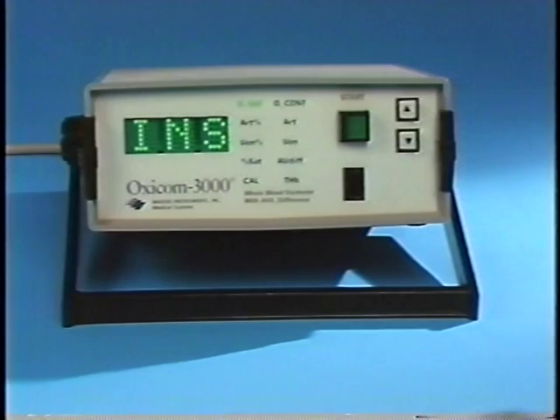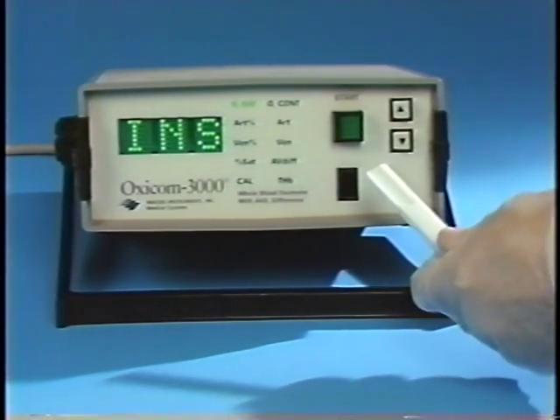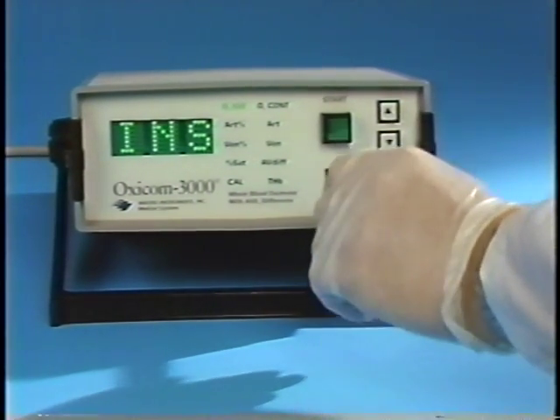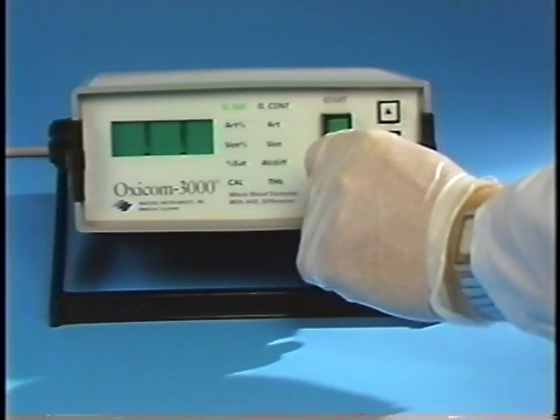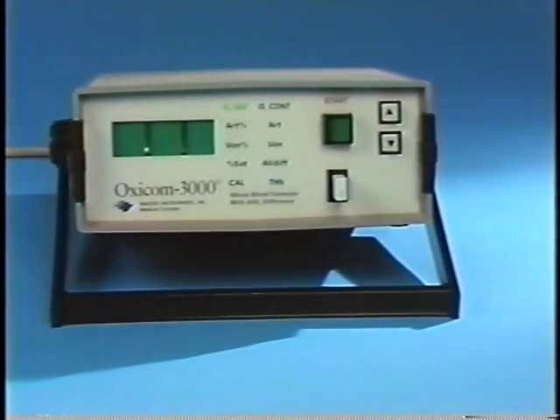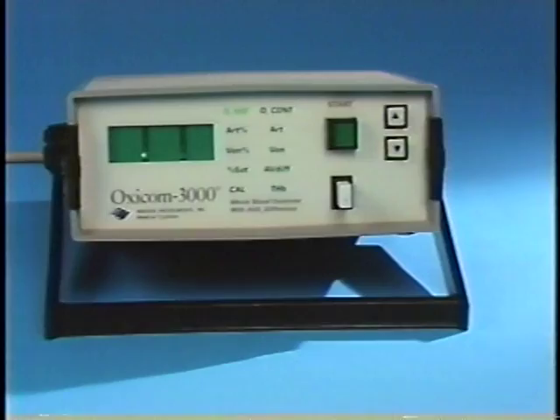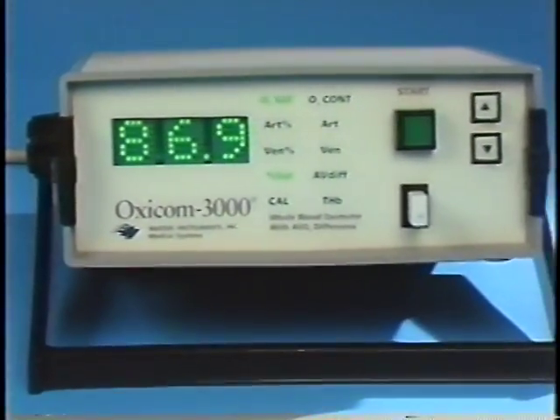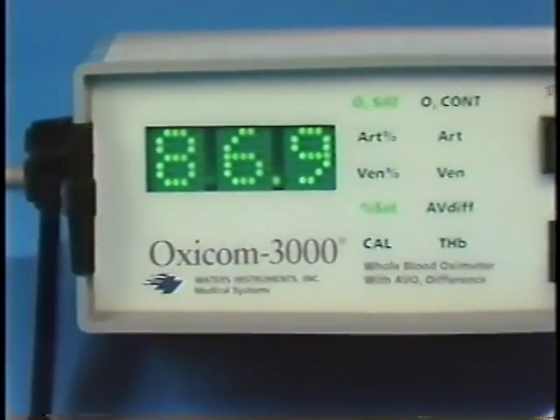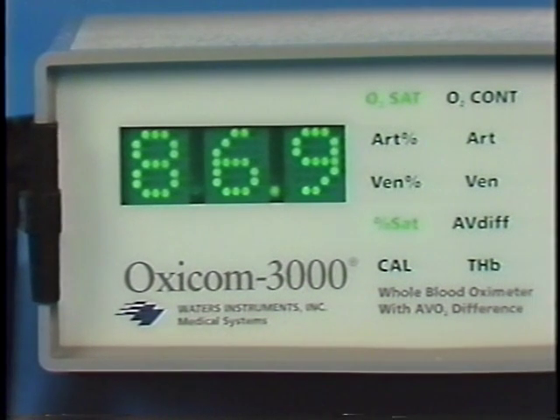The white Delrin stick is attached to the unit for daily verification of the oximeter. After calibration, insert the Delrin stick into the sample port 5 times and record each value. Record that average on a data sheet as a standard. The Oxicom 3000 can be unplugged and moved back to your cath lab with the calibration locked into memory.